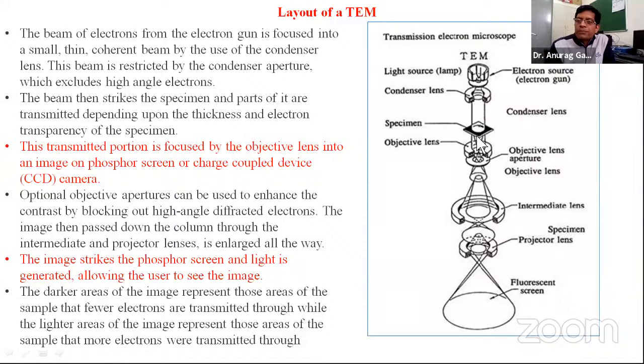After the transmission, there is the objective aperture. The objective aperture basically stops some of the high angle electrons, otherwise the image will be blurred. Then the objective lens will project the image, and it is further magnified by the projection lens, and this image is projected onto this fluorescent screen, and then we can see the image. So this is the basic working. The beam that strikes the specimen is partly transmitted, and it depends upon the thickness as well. So the electron transparency of the specimen is very important.